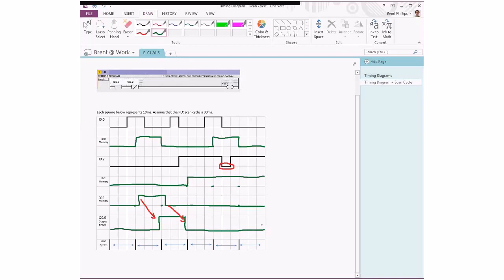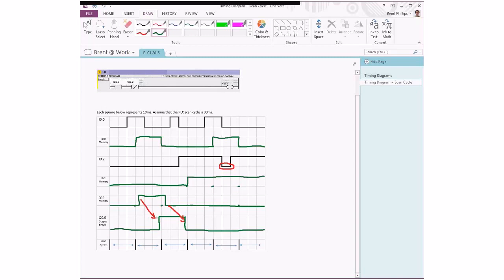So if you're careful with these ones, looking at the different stages of the scan cycle: the first stage is transferring the physical input value into the memory for the PLC. The second part is using the combination of the memory values to create a memory value for the output based on whatever the ladder logic tells us to do. And the third part is transferring that memory value for our output to the physical output circuit, just at the very last part of the scan cycle.